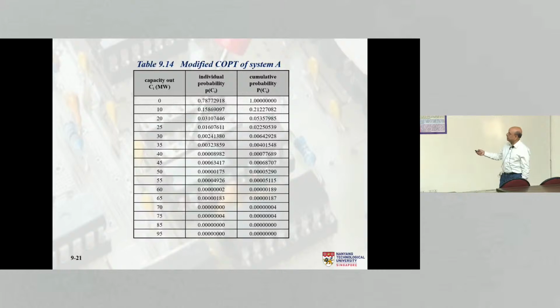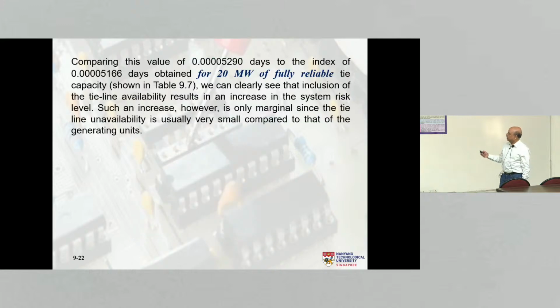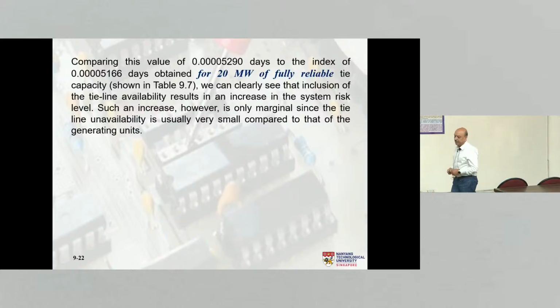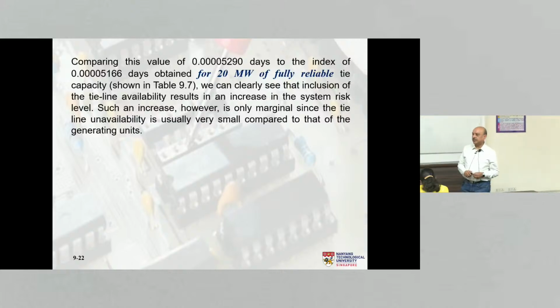Okay, and then we obtain the modified COPT, and then the cumulative probability of 50 or more out is this one, 0.00005290. That's the risk in the system, the new risk in the system. Clear? Okay. So compare this value with the original index obtained for 20 megawatt of fully reliable tie capacity. We can see that the inclusion of the tie line availability results in an increase in the risk expected. We are quantifying the increase. We expect that the risk will increase surely. So such an increase is only marginal since the tie line unavailability is usually very small. As I mentioned, tie lines are fairly reliable.